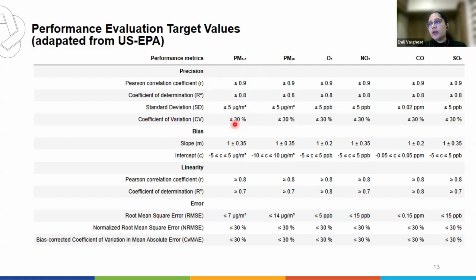Now, when we want to compare a PM sensor against the reference instrument, we consider the slope and intercept for bias. For the slope we consider 1 plus or minus 0.35, and for the intercept, between -5 and 5 micrograms per cubic meter. For linearity we consider R greater than or equal to 0.8 and R square greater than 0.7. For RMSE, less than or equal to 7 micrograms per cubic meter. Then for NRMSE and CV, we consider less than or equal to 30%. So these are the different target metrics which we can use for comparing our sensors with the reference instruments, and this helps us validate the performance of the sensors.